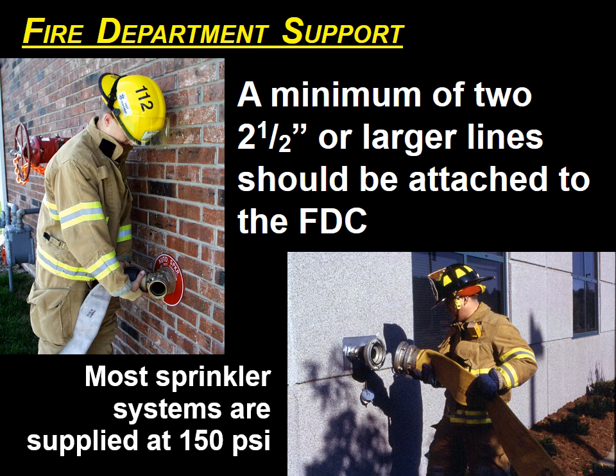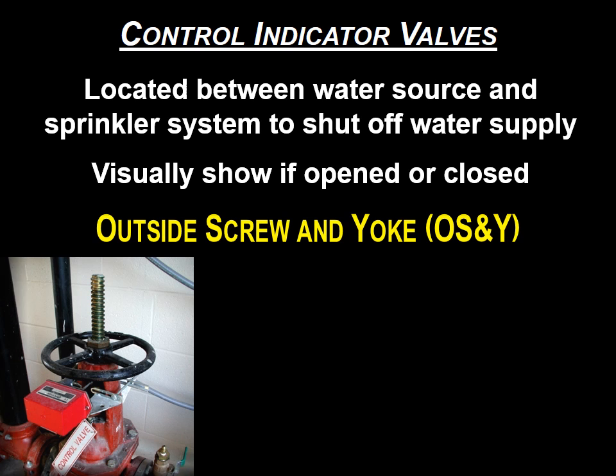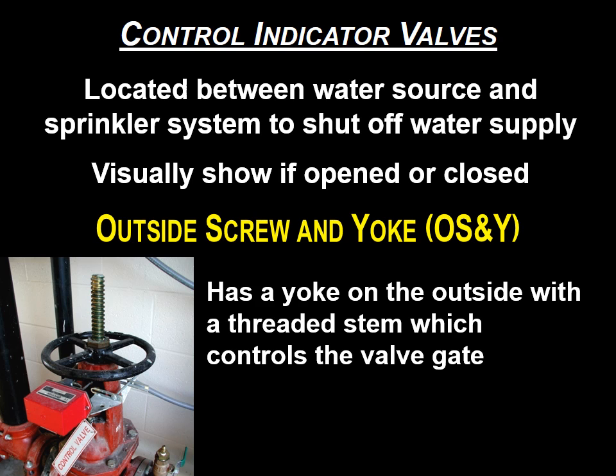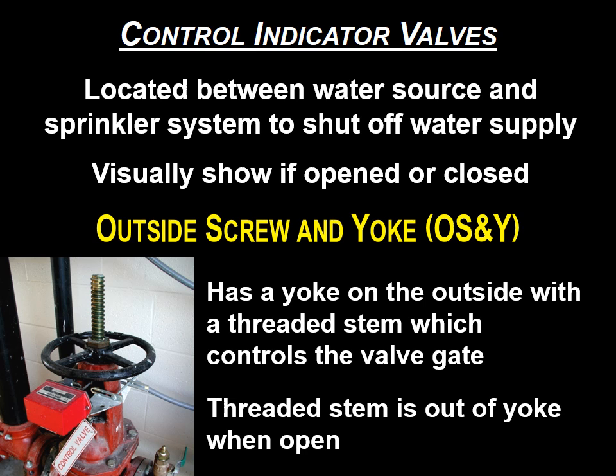Most sprinkler systems are supplied at 150 psi. Control indicator valves are located between the water source and the sprinkler system to shut off the water supply, and they will visually show if open or closed. Our outside screw and yoke has a yoke on the outside with a threaded stem which controls the valve gate. The threaded stem is out of the yoke when open. So currently in this picture, the valve is open.